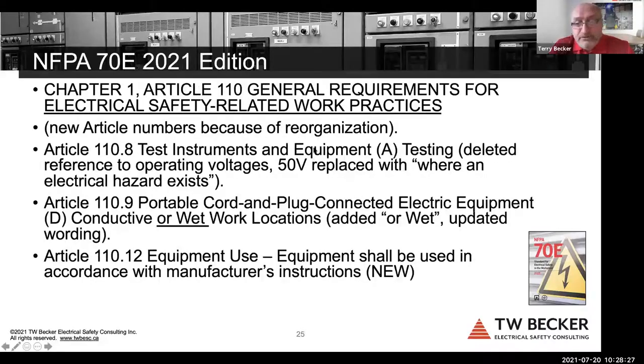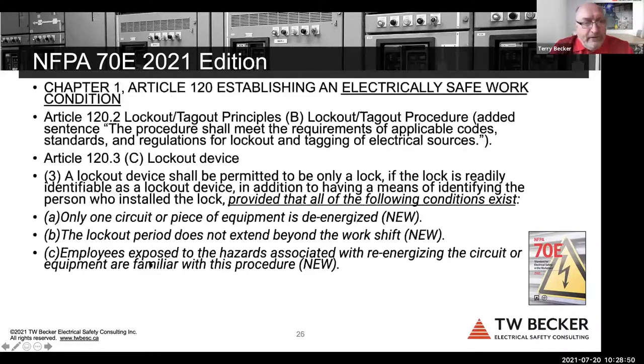All right, so test instruments, just some minor wording changes here, eliminating the 50 volts and just saying where an electrical hazard exists, adding the word wet locations for the use of a GFCI with portable cord and plug connected electrical equipment. And new text added to Article 110.12 says equipment shall be used in accordance with the manufacturer's instructions. Now we're moving into Article 120. So again, I'm just highlighting the key changes. Like I said, there really wasn't a lot of technical changes. It was more of this huge structural movement of content, and really, it's amazing. If you really read it and you get it, you're going to say this now makes more sense than it ever did before when I review Article 110 or Clause 4.1 in Z462.